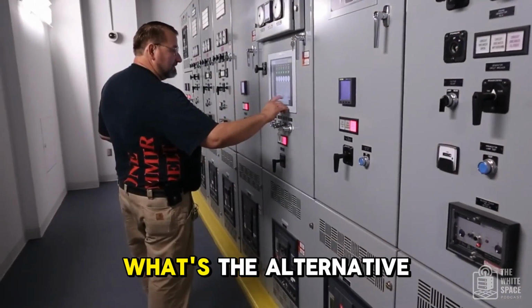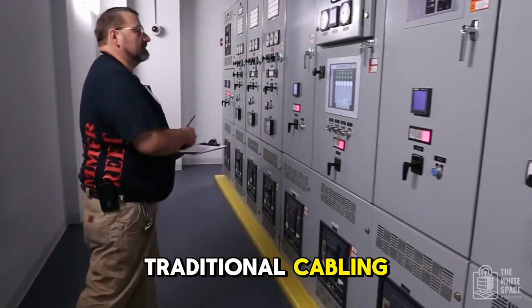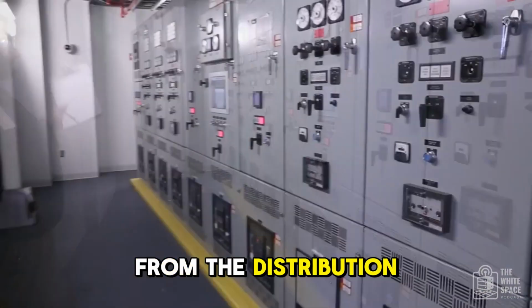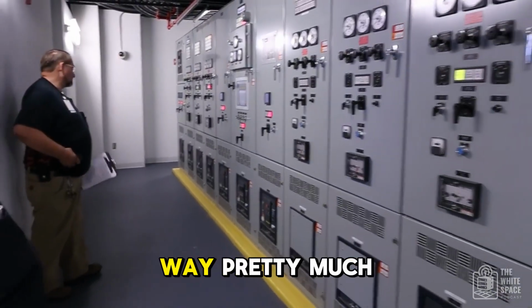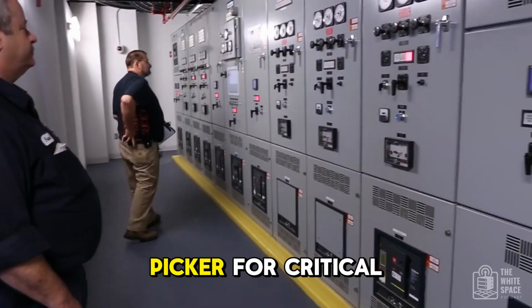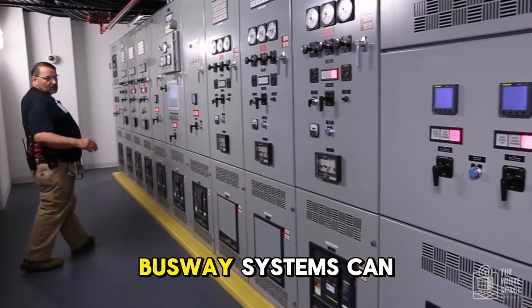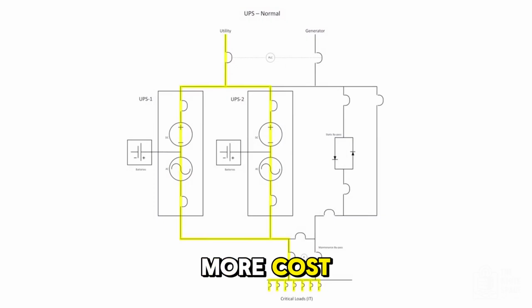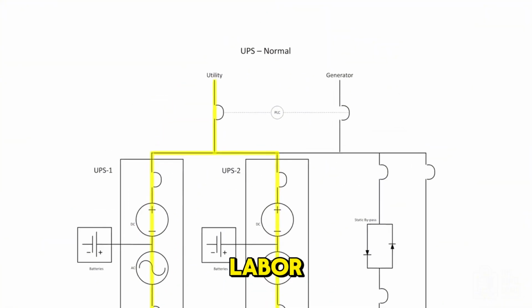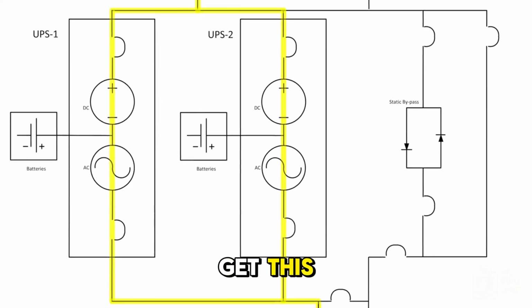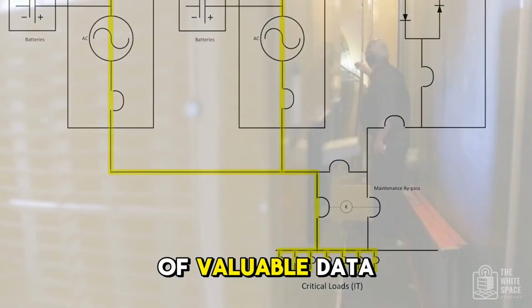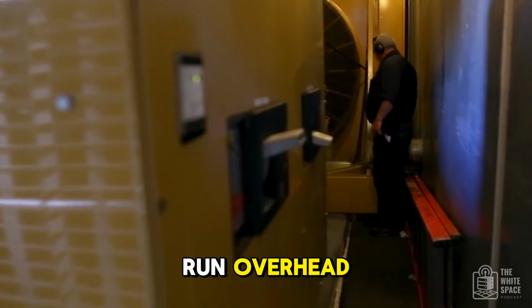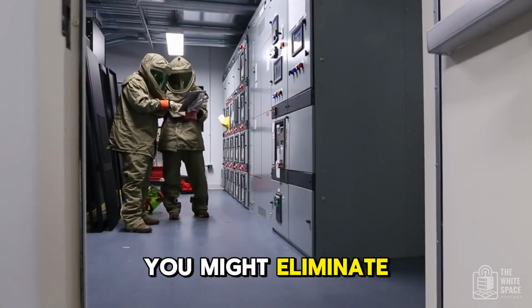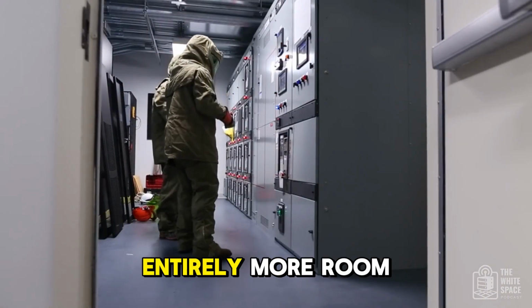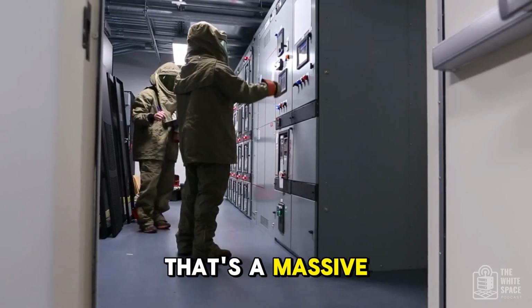Okay. Busways. What's the alternative? The alternative is traditional cabling, running individual conduits and wires from the distribution panels to the racks. The old school way. Pretty much. Still used, of course, but here's a kicker. For critical power distribution, busway systems can be almost 60% more cost-effective than traditional cabling. 60%? Why? Faster installation, less labor, more material efficiency. Plus, get this, busways can free up about 8% of valuable data center floor space. How? Because they often run overhead, feeding RPDUs directly, you might eliminate the need for those big floor-mounted PDUs entirely. More room for servers. That's a massive advantage.